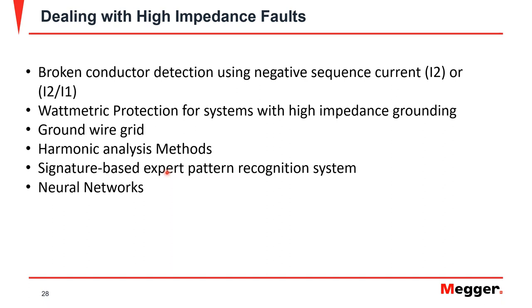Since high impedance faults contain high harmonic content, harmonic analysis can be used to determine whether such a fault exists. Patented methods like signature-based expert pattern recognition systems are used by some manufacturers in partnership with universities. There is also a resurgence of research using neural networks as pattern recognition systems for the detection of high impedance faults.